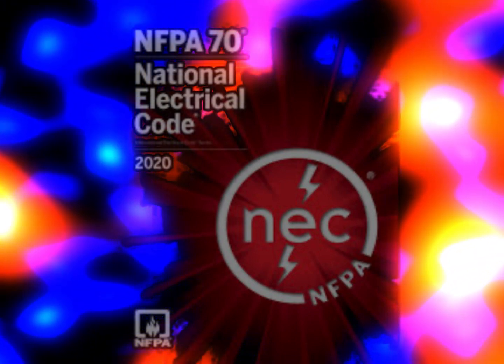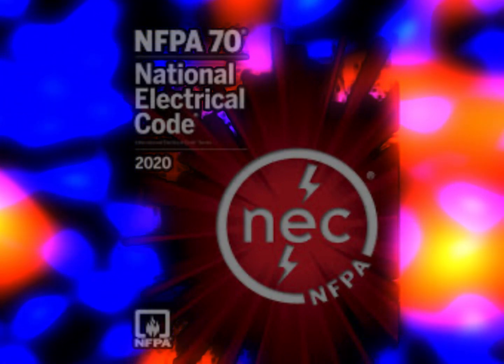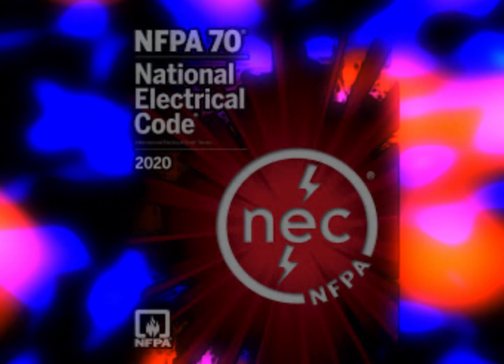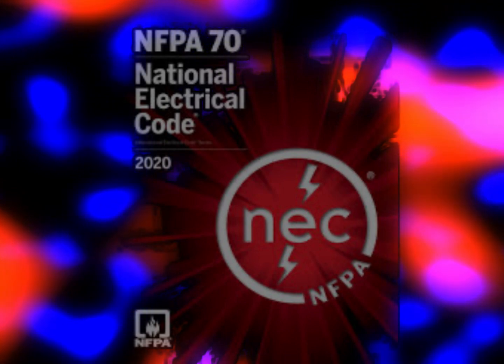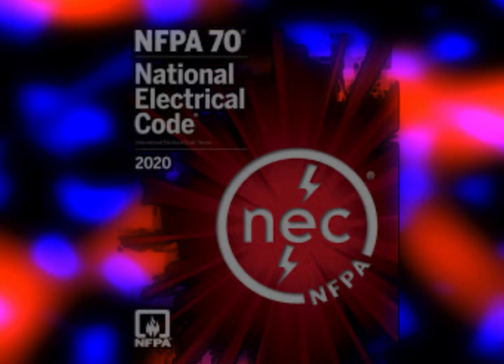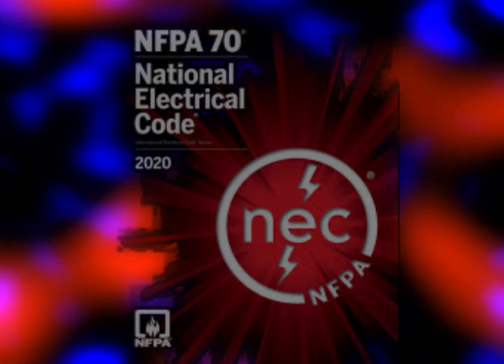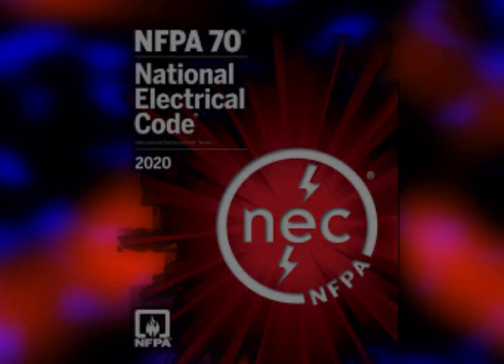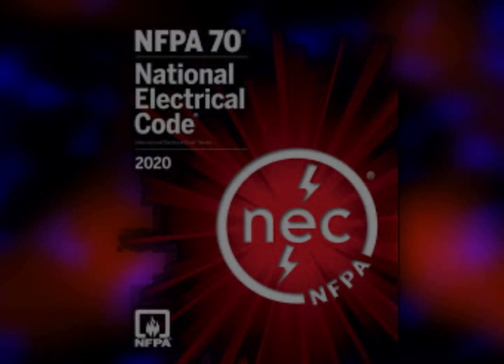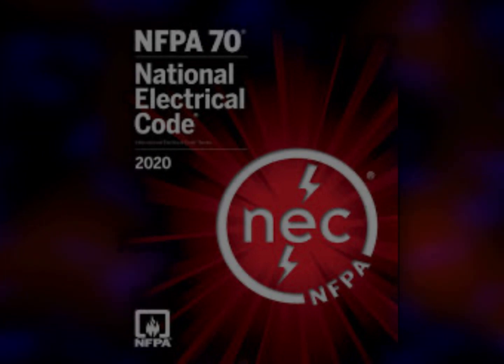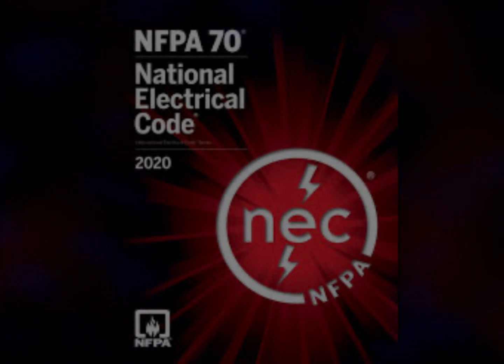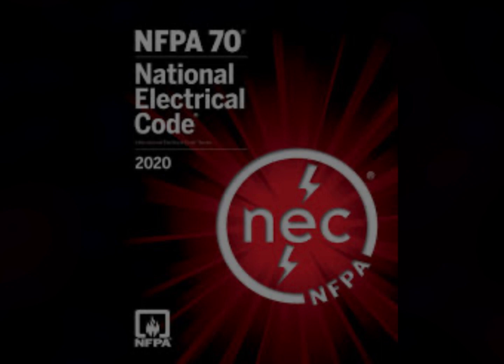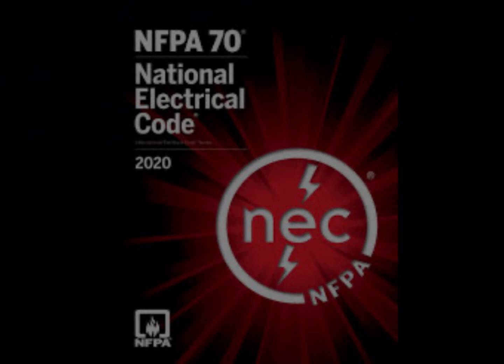Associated apparatus that identify intrinsically safe connections to intrinsically safe apparatus and also have connections for non-intrinsically safe apparatus. An example of associated apparatus is an intrinsic safety barrier, which is a network designed to limit the energy, voltage, and current available to the protected circuit in the hazardous classified location under specific fault conditions.